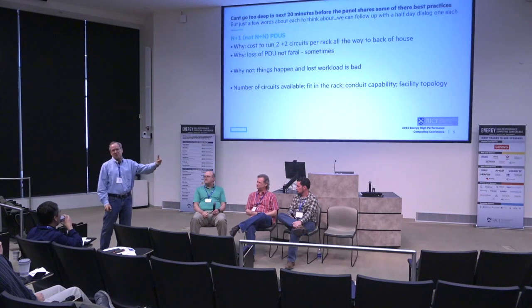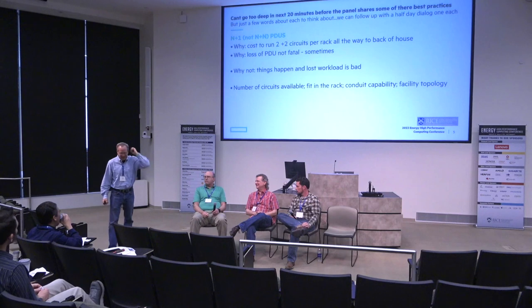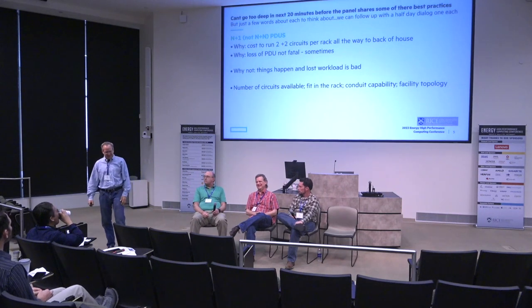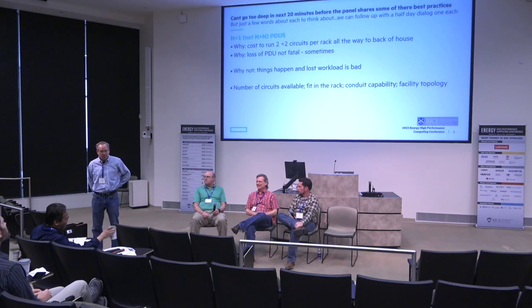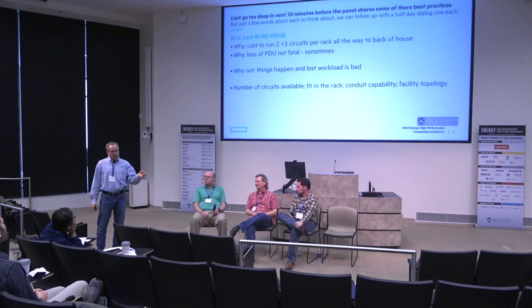So if in Europe you get 125 amps out of a plug, you only get 80 amps in the U.S. At 415, 240, I don't know, can we influence the industry to change that? It's sort of ridiculous. But what it means is that only at 480, 277, each 150-amp circuit is exactly 100 kilowatts.